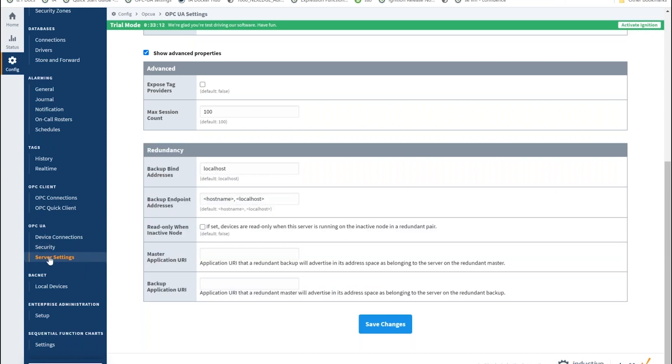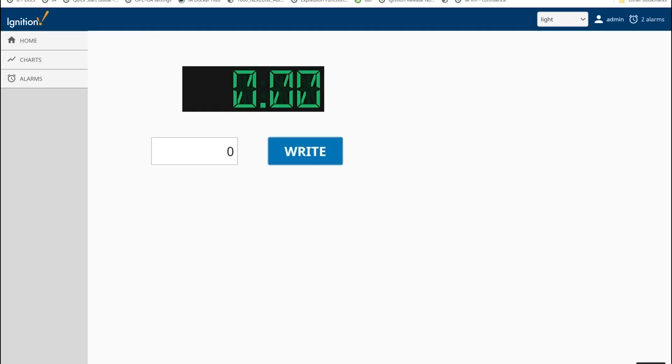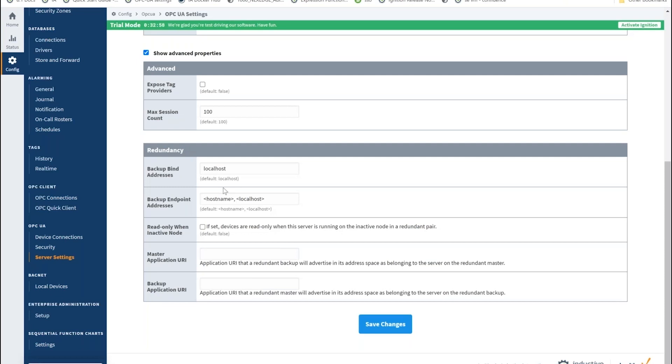We do have some settings here if you do want to configure that under the server settings advanced options, so you can go through your own system and set that up. One quick note there that I wanted to make: in addition to the settings that Matt was just showing that have to do with Ignition's redundancy and how the binding works there with the different OPC servers, the support for the OPC redundancy that is based on the OPC spec is actually not directly tied to what we're looking at here.